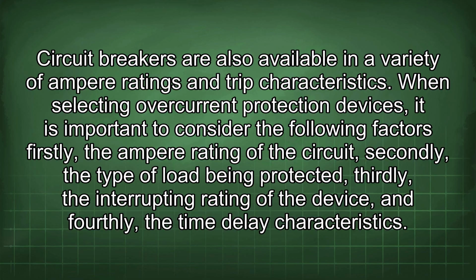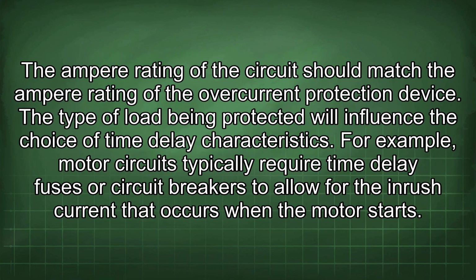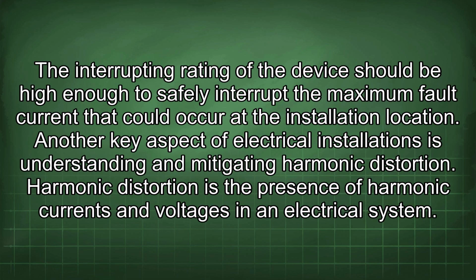Firstly, the ampere rating of the circuit. Secondly, the type of load being protected. Thirdly, the interrupting rating of the device. And fourthly, the time delay characteristics. The ampere rating of the circuit should match the ampere rating of the overcurrent protection device. The type of load being protected will influence the choice of time delay characteristics. For example, motor circuits typically require time delay fuses or circuit breakers to allow for the inrush current that occurs when the motor starts. The interrupting rating of the device should be high enough to safely interrupt the maximum fault current that could occur at the installation location.